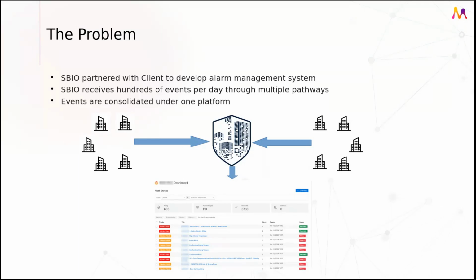Regardless of whose system is in the building and what type of alarm they're sending, it could be a temperature alarm saying a room is too hot or too cold, or an equipment alarm saying a chiller or air handler has failed. They could even be security alarms saying a door has been left open. All of these alarms are fed under one single dashboard for operators to view.